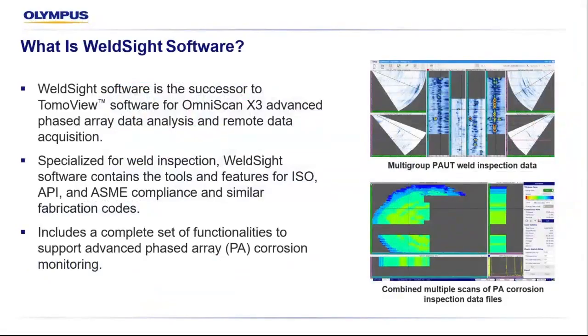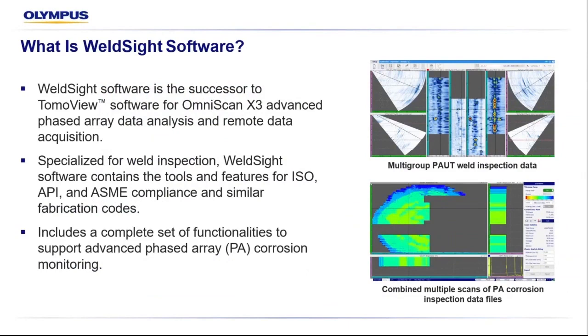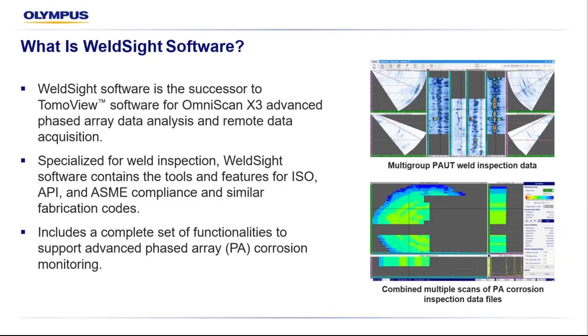What is the WeldSight software? Before we dive into the new Remote Connect feature, let's touch on what WeldSight is and what it has to offer for the X3 user. The WeldSight software is a successor to TomoView for the X3 advanced phased array data analysis and remote data acquisition. Specialized for weld inspection, WeldSight software contains the tools and features for ISO, API, ASME compliance, as well as other similar fabrication codes. It includes a complete set of functionalities to support advanced phased array corrosion monitoring and mapping.